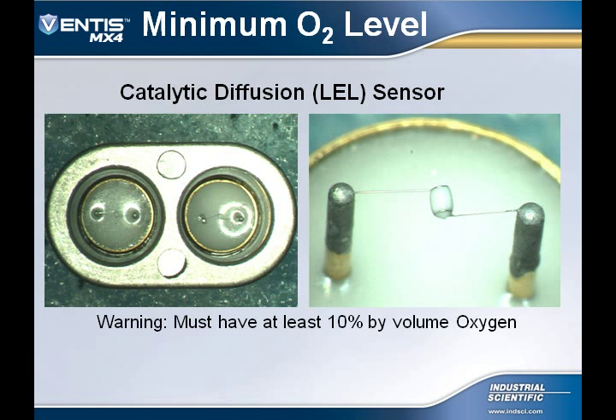One thing to remember is that you have to have 10% by volume oxygen for the sensor to operate. This is because the sensor actually burns the gas and we need oxygen to aid in the burning process.